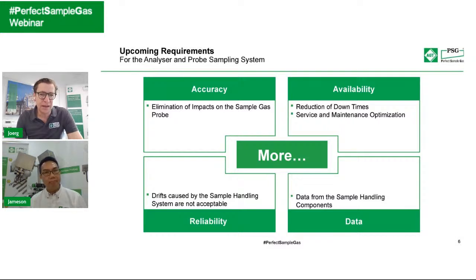And if it's a CEM system, a continuous emission monitoring system, there are certain predefinitions of the time, the uptimes of the system. And so the availability will become very important as well. Reliability, I think, is something which is important, that there is no drift in the system after the commissioning is completed and the go-live has happened. We have to ensure that the accuracy remains. And also, I think the data-driven world will increase, and the demand for data, also from the sample handling system, will increase.